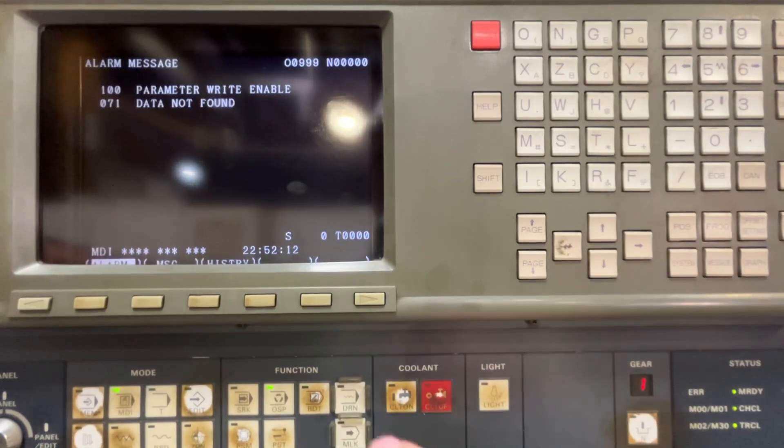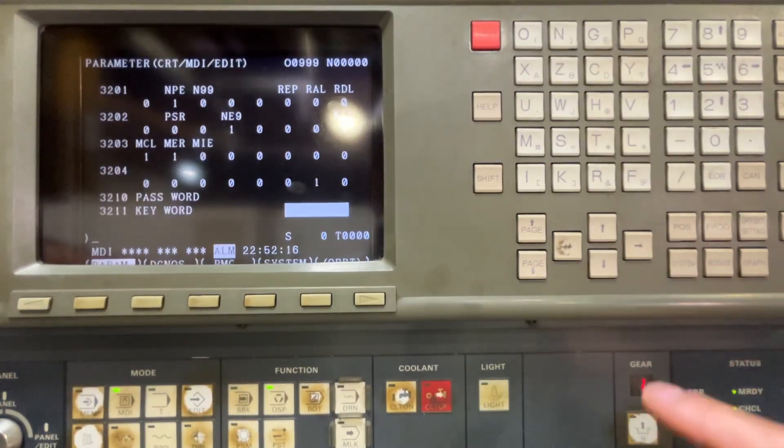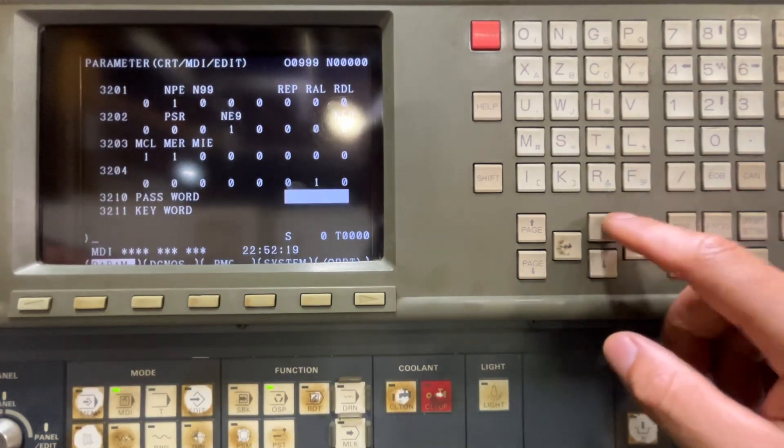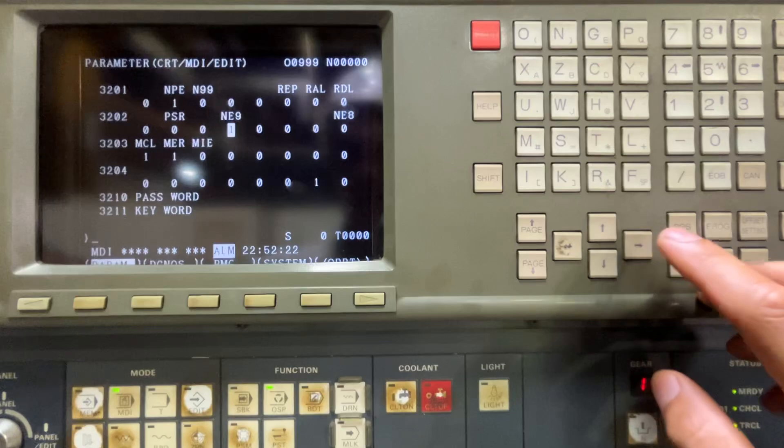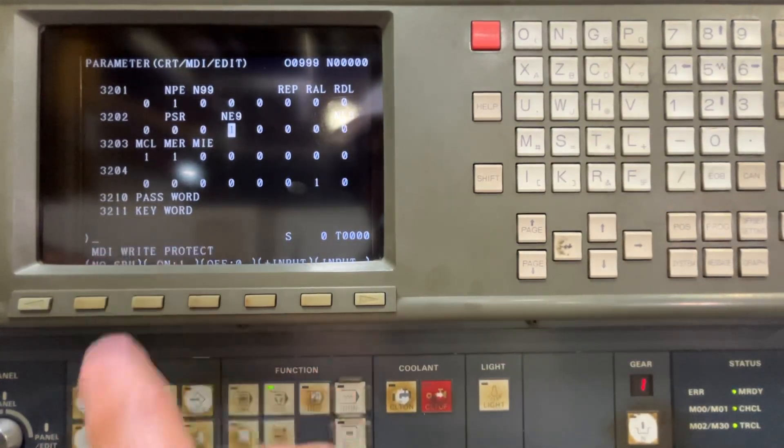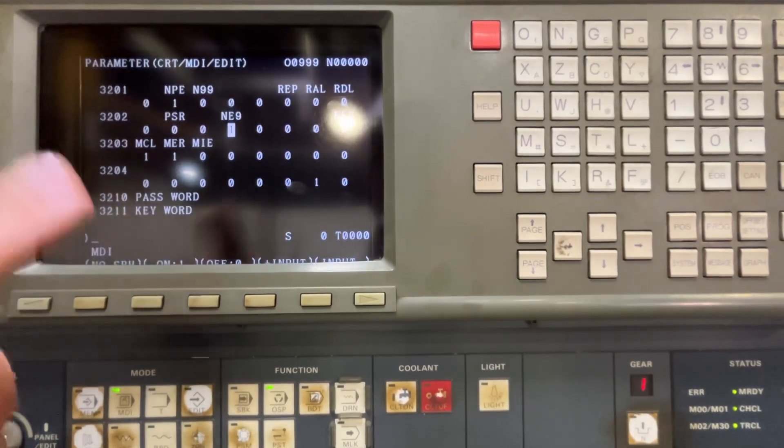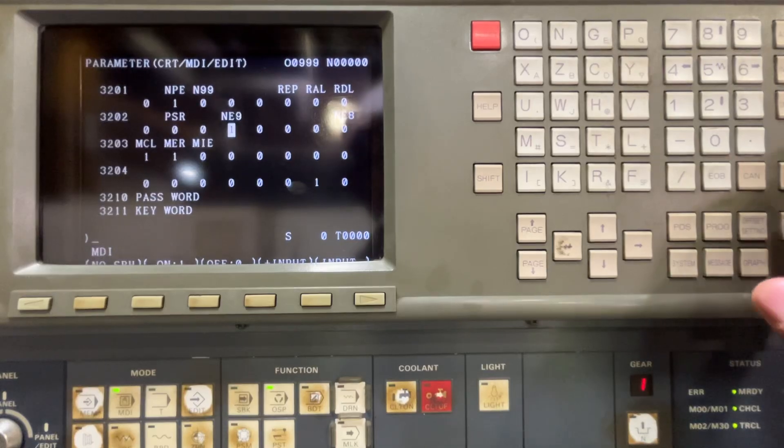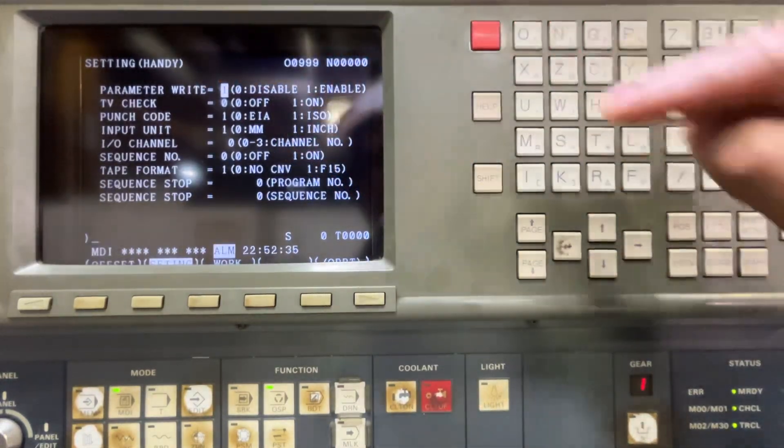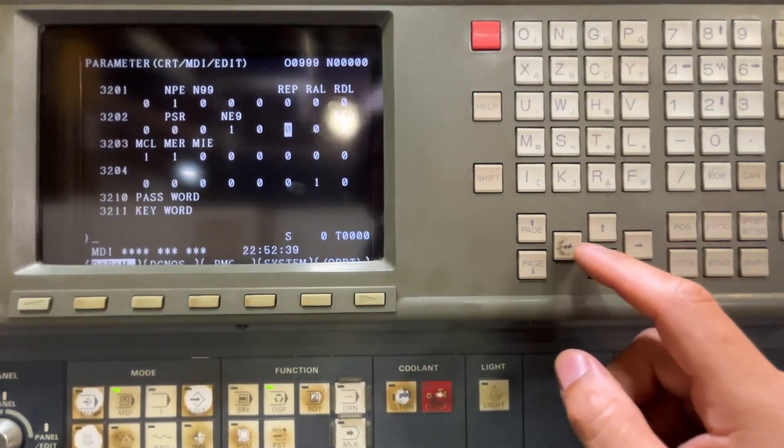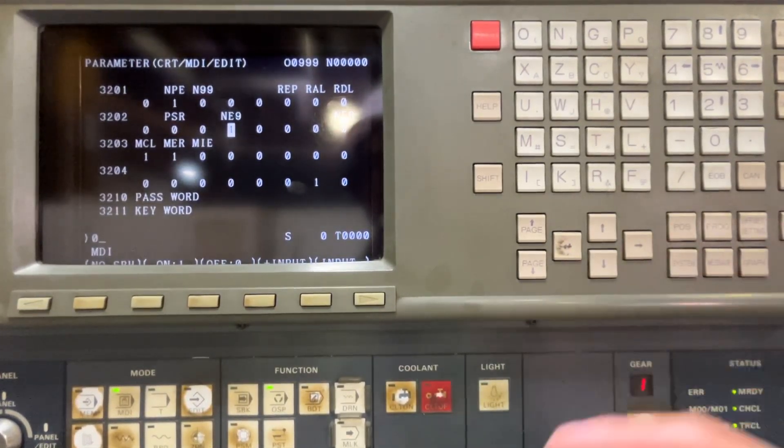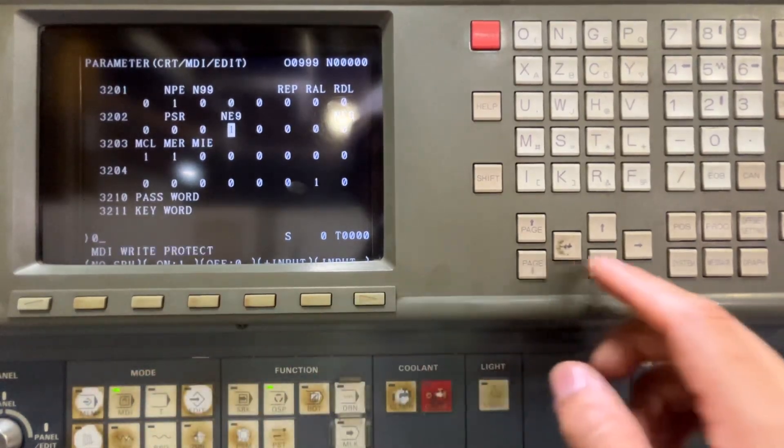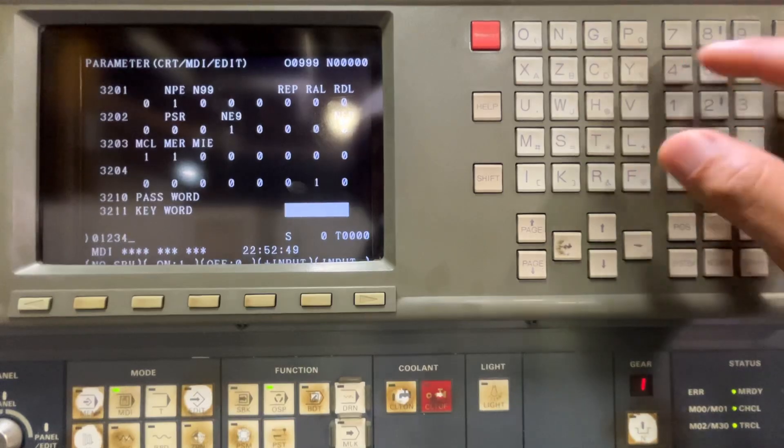Input, input. I'm going to reset the alarm. Let's go back to system. And if I want to change this one to off, you see, even though I set the parameter write enable, it doesn't allow me to modify this bit. Let me try. Input again. So what I have to do is enter the password here, 1234.